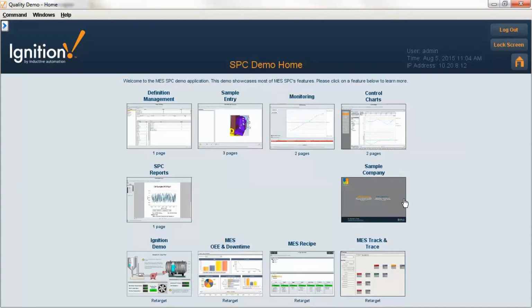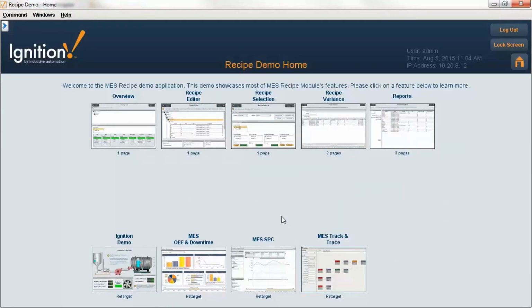The next module we're going to look at is the recipe module, which allows you to load recipes down to the PLC. It's a very simple one-time load of the recipe, not a batching system at all. It's designed to work with the OEE, downtime, and track and trace modules, so when we start a production run for OEE, we can load a recipe down on a changeover based on the product selected. But it can also stand alone as a simple recipe system.